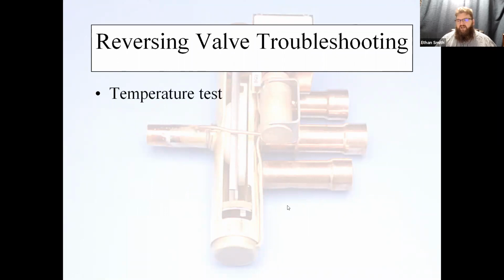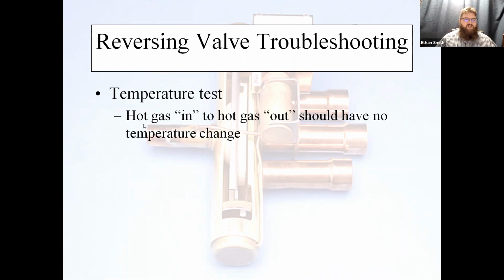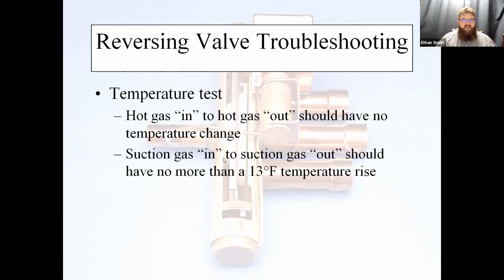The most reliable method to diagnose a mechanically stuck reversing valve, assuming that those other conditions have been met, is a temperature test. So your hot gas in to your hot gas out should have virtually no temperature change. Your suction gas in to your suction gas out should have no more than a 13-degree temperature rise through the reversing valve. It's always going to have some temperature rise just because of the nature of how the valves are built. It's going to transmit heat into that suction line. But if you've got more than 13 degrees of rise on your suction line through that valve, that means that seal has either failed or the reversing valve is stuck and only partially engaged. And so that's going to cause excessive heat into your suction line returning to the compressor. So that's the sure way to see that you've got a stuck reversing valve.